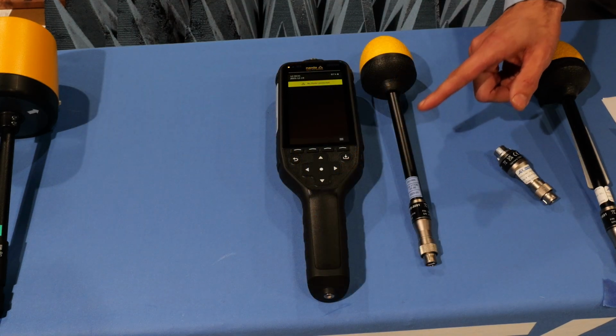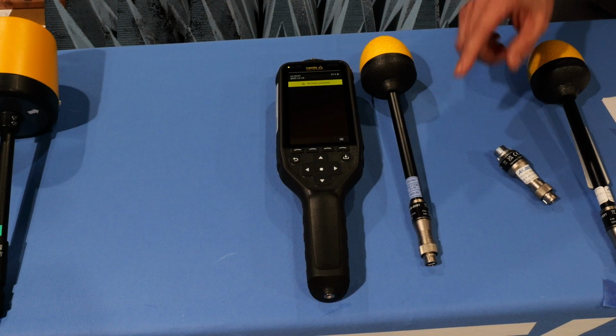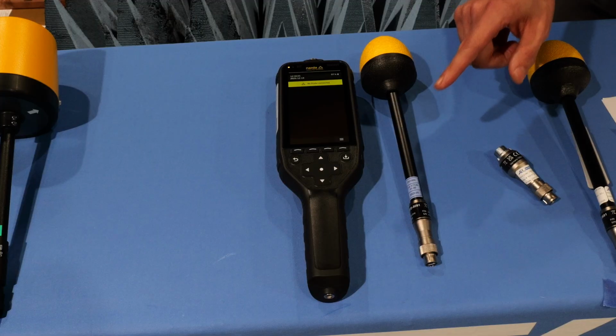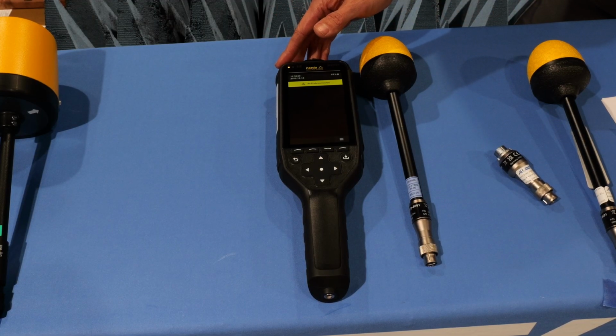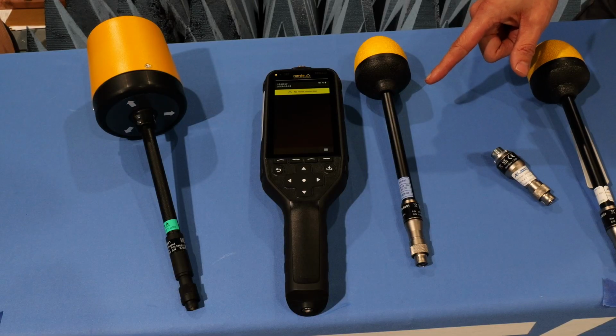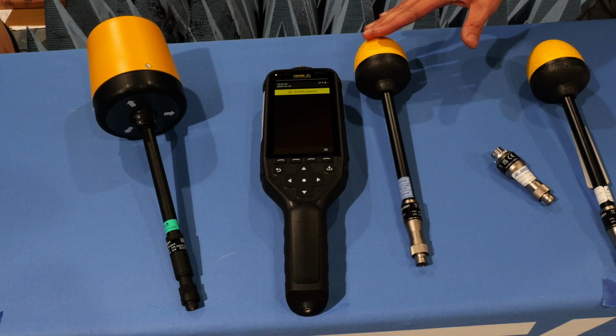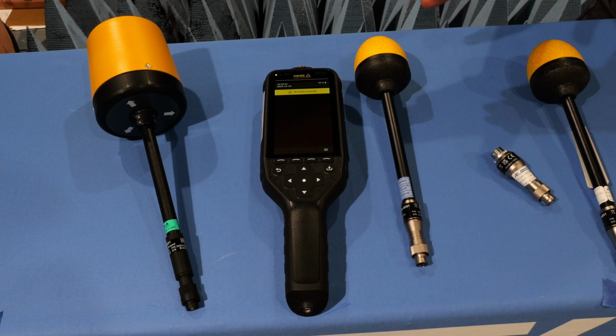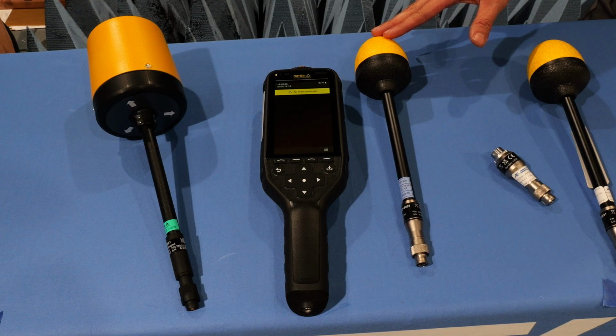Since the new digital probes integrate all these functions, only the probes need calibration. The FieldMan meter does not need to be calibrated, which saves time and money. Also, since the digital probes integrate these functions, they can be connected directly to a computer and used with the free Narda TSX software.